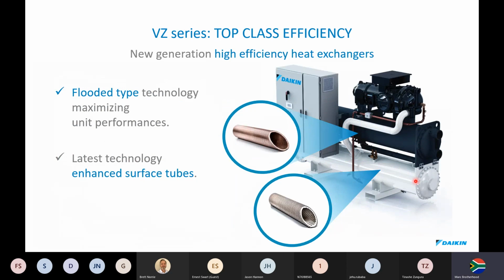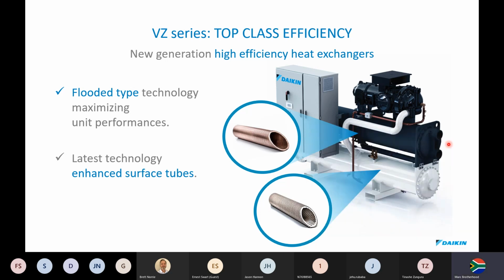The condenser as well as the evaporator are flooded type technology, and we use rifling on the tubes. The reason we use rifling is we create hills and valleys, these little corrugations in the pipework, and what they allow for is better heat transfer. We're increasing the surface area for heat transfer without having to make the condensers longer. So we maintain the same size. Sorry, just give me a second. I just had something come on my screen there. But by having rifling, we increase the surface area without having to make the chiller bigger.